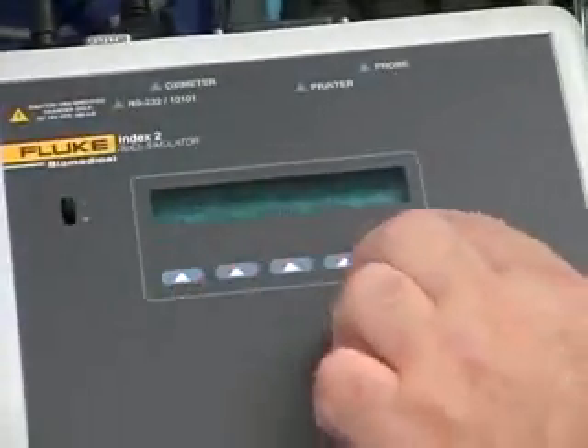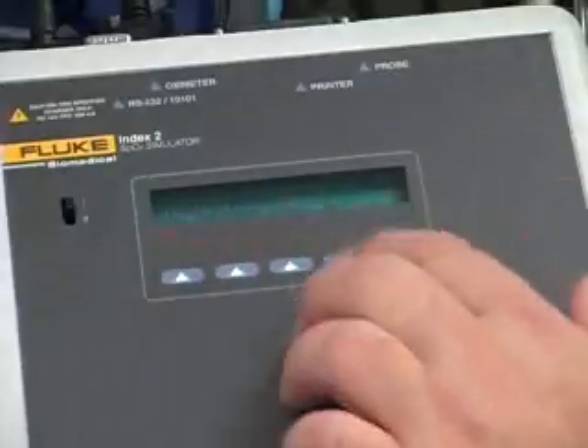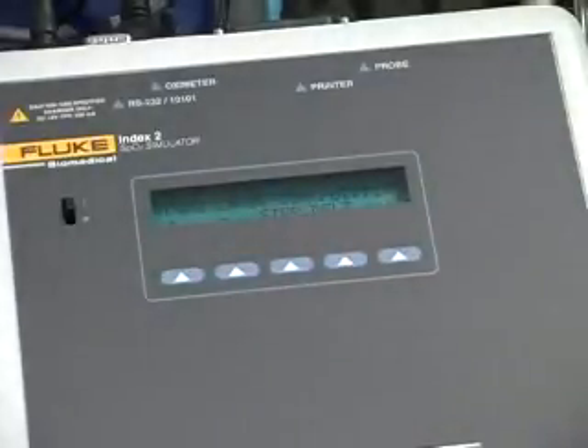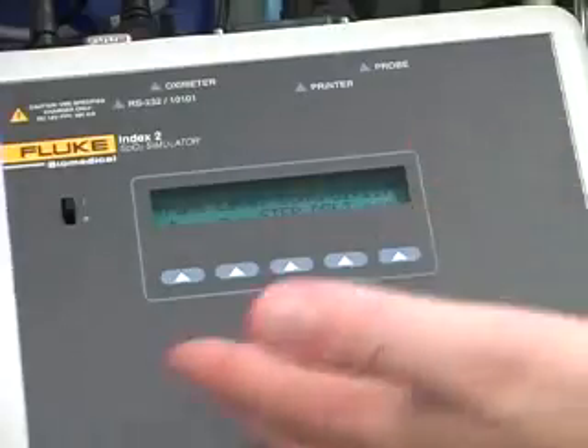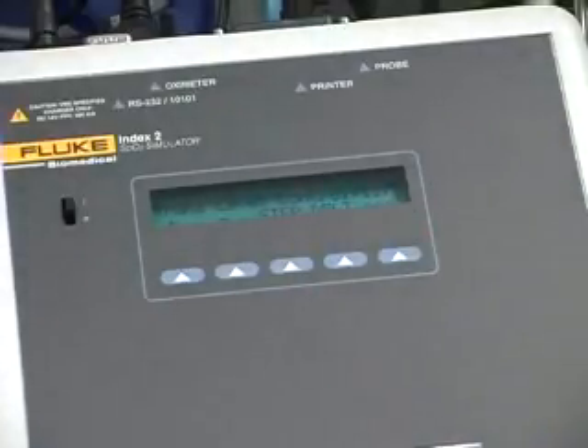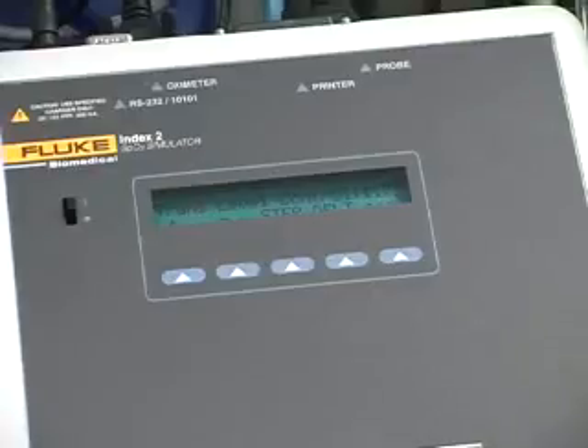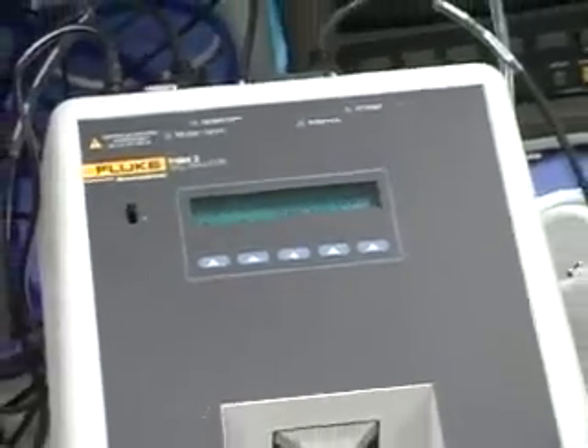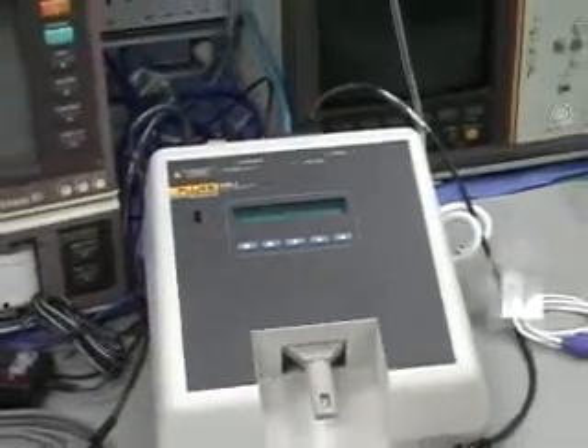But like I said, anytime you have problems or you're seeing issues with pulse amplitude, just go into the TLC and see what the numbers are. If they're low, which would be anything from 500 to about 1,200, just go in there and jack them up to about 3,000. All that's doing is giving you a stronger signal by giving you less simulated tissue for the lights to go through. You're putting lower resistance on the light sources, so you will get a higher amplitude signal.